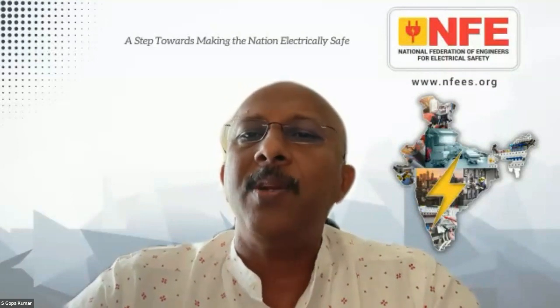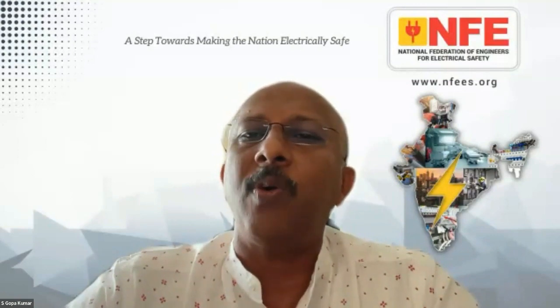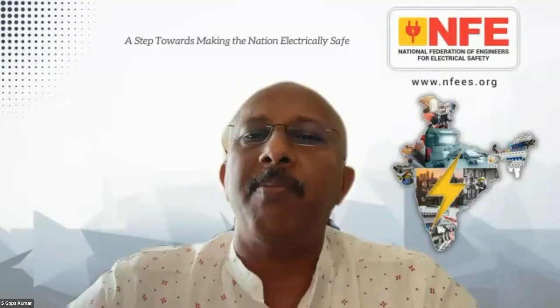So, is it necessary to connect resistance earthing to an 11 kV 415 volt 5000 kVA transformer, or is solid earthing sufficient? Please clarify. Sir, what is the vector group of the transformer? If you are talking about the 415 volt side, definitely solid earthing, only solid earthing. Don't go away from that. By regulations, you are supposed to connect only by solid earthing on the 415 volt side.